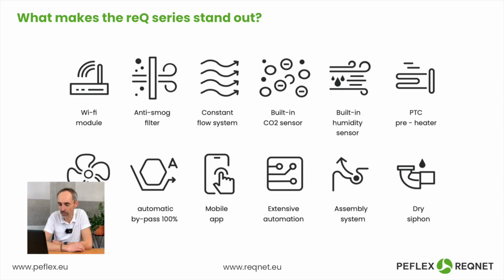The next component that also benefits the user is the constant flow module. The task of the constant flow module is to keep the air streams on the supply and exhaust sides at the same level, in order to maximize the heat recovery efficiency of the exchanger.